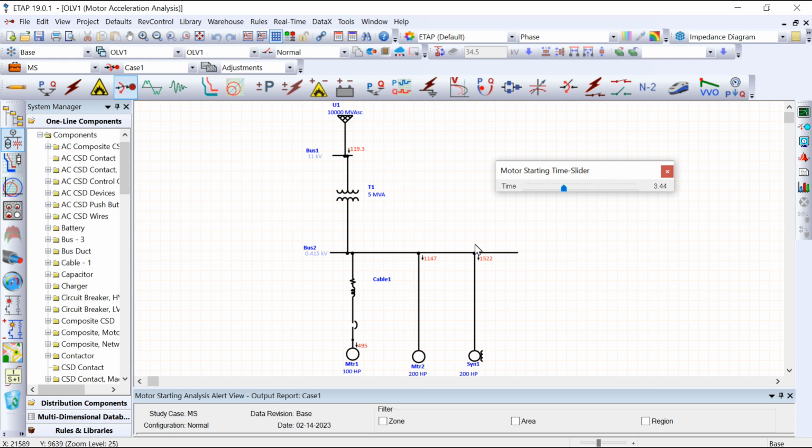And it's the same with synchronous motor 3. It started with 1,500 something. Then it will continue to go back to normal. As you can see now, motor 1 goes back to normal, and motor 2 also goes back to normal after a couple of seconds. But we can see what the influence is on our bus in this case.